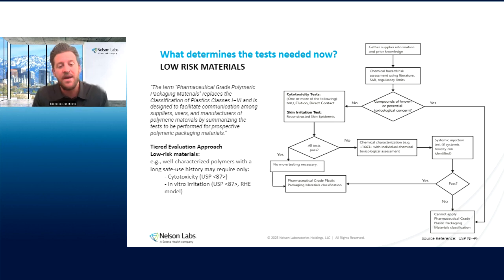If those tests do not pass, we would start to look at chemical characterization, utilizing USP Chapter 1663, with an individual chemical toxicological risk assessment or a chemical safety assessment, or a combination of those two, which we'll talk about briefly momentarily. If needed, our systemic injection test would then be leveraged. As we talked about earlier in our in vivo chapter, we do still have our systemic injection test listed, but we are going to try to really postpone using that test until it's absolutely necessary. And if all passes there, then we can apply our new terminology to our material.